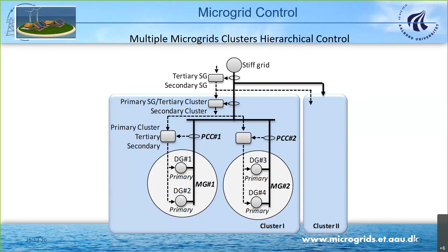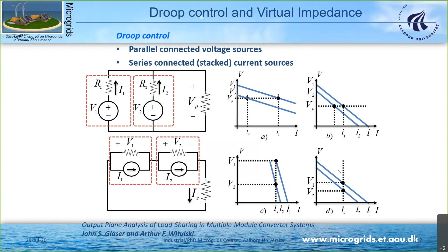Coming from AC, we can see similar things on DC. So when we talk about virtual inertia, in DC systems we don't have frequency, which means we just have two variables: basically current and voltage, or you could think power and voltage. This means we can also integrate droop controllers by measuring the current and drooping down the voltage. The same way we use reactive power Q versus voltage, here we can use current versus voltage in order to have those droops and connect a number of voltage sources in parallel.